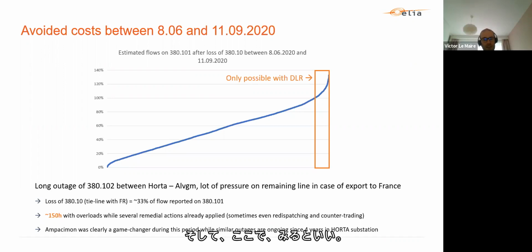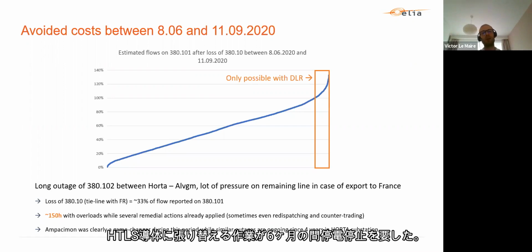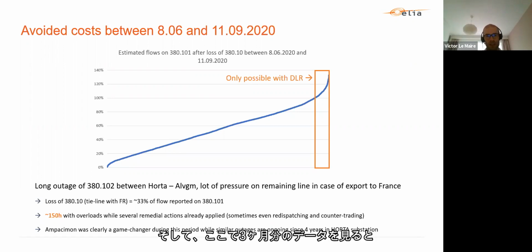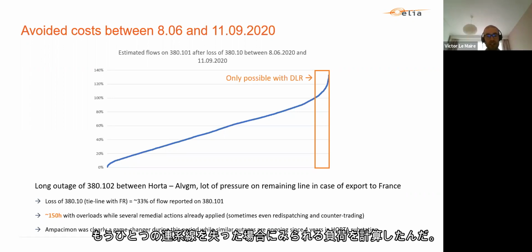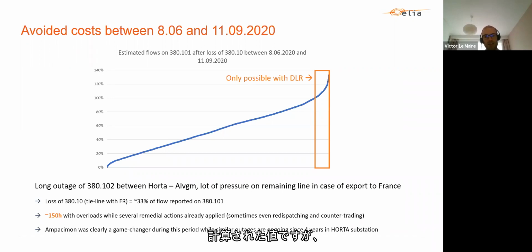Here I think it's good to see one example of the lines where HTLS works on a specific line. As I said, we had a tremendous outage of 6 months, and here I see data from 3 months where we had an outage and the parallel line was heavily loaded. This is a line between France and Belgium, and I computed the load this line would have seen after the loss of another tie line between France and Belgium, showing the flows after the incident.